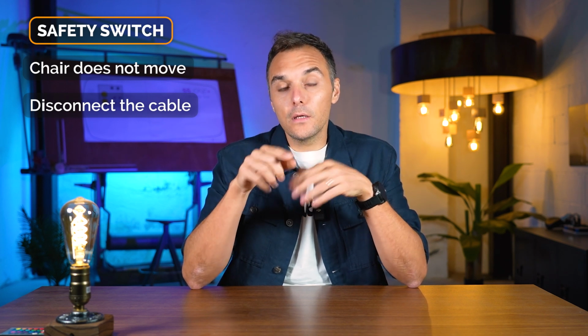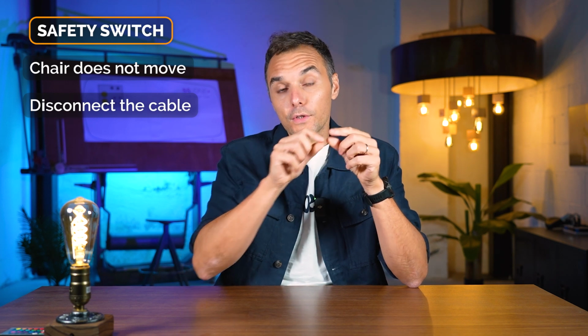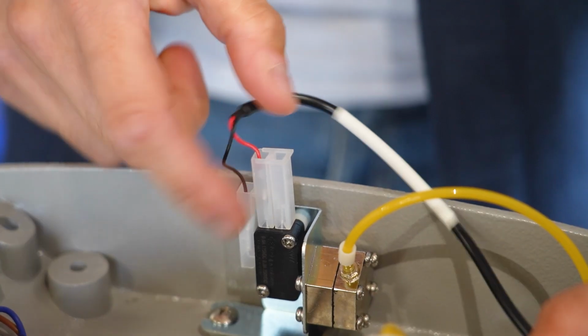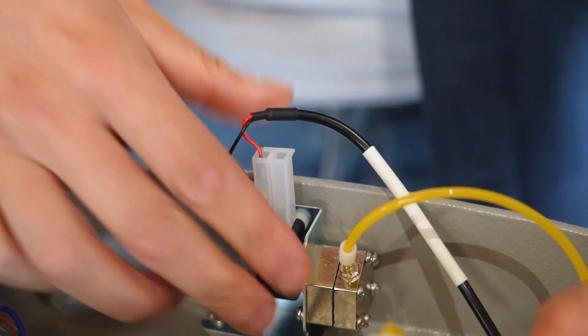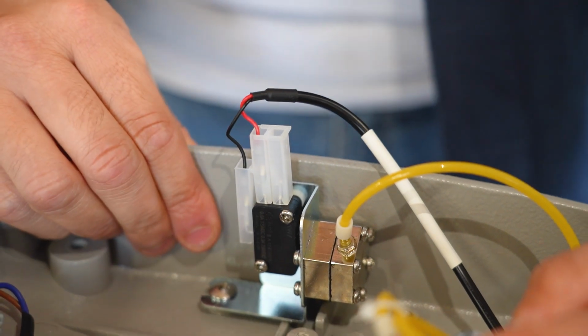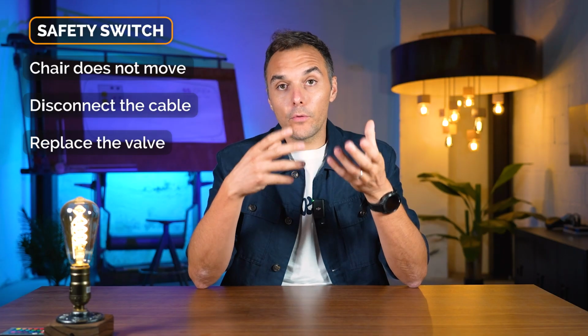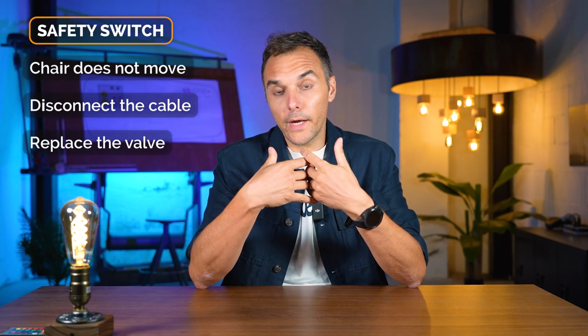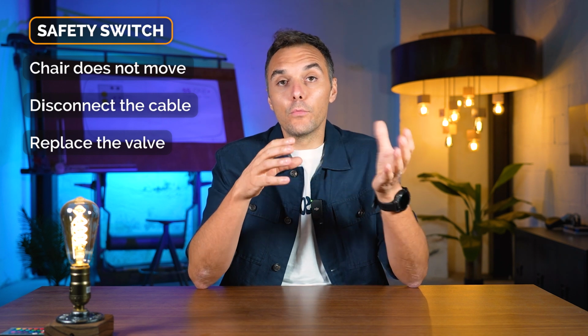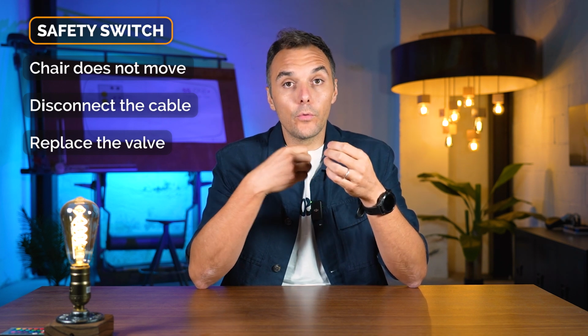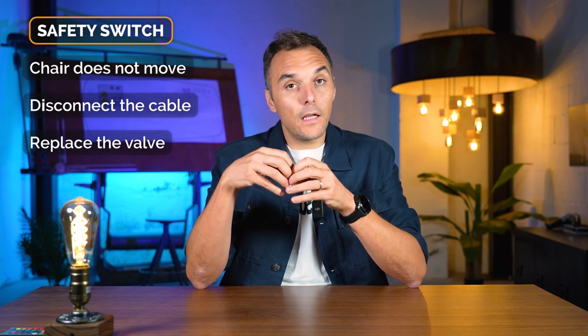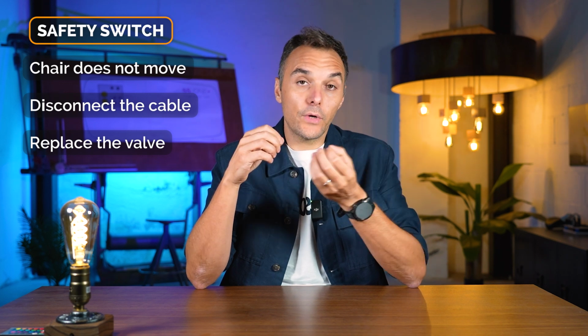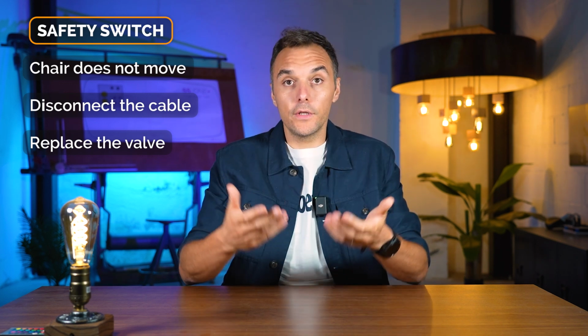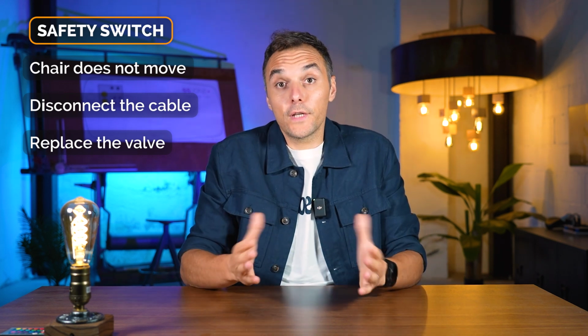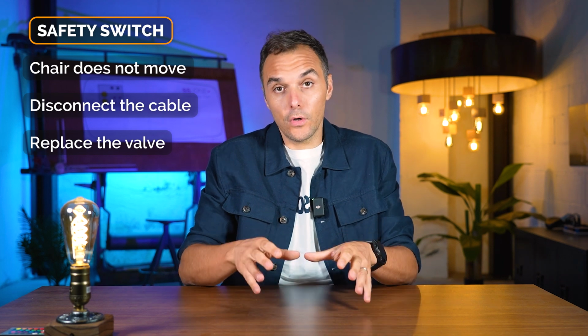In this case it can be this cable, and at the end of the cable there is also a valve that activates or deactivates this function on the unit. Normally when the chair performs correctly, you cannot move the chair while the doctor is operating. But in case the valve has some problem, disconnecting the cable lets you avoid this function temporarily, until you solve the problem.